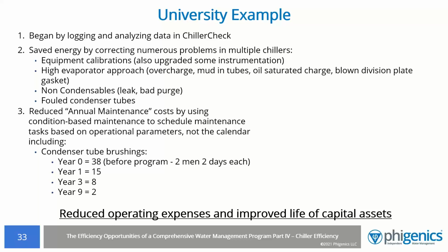The change in their maintenance procedures over the years: before the program, they were brushing every chiller, 2 men, 2 days per chiller to drop heads and brush tubes. After the first year, using the new water program implementation and the new logging process, they only had to brush 15 of the 38 chillers. And then from there, it dropped down to 8 chillers in year 3, 2 chillers in year 9. So the savings just in manpower was big. The savings in energy was huge.